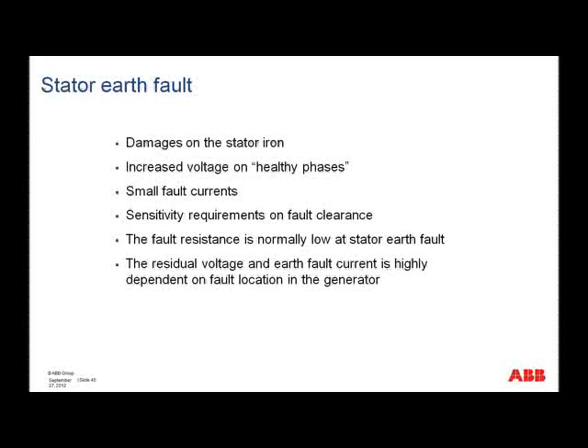All right, let's have a look now at the stator earth fault. You remember from very close to the beginning of the presentation, we spoke about possible damages to the stator iron, and hence the need to limit the stator earth fault to a reasonable small value, from around about 10 amps primary. Because of this high resistance earthing, when we do get the stator earth fault, we get increased voltage on the healthy phases, and small fault currents.